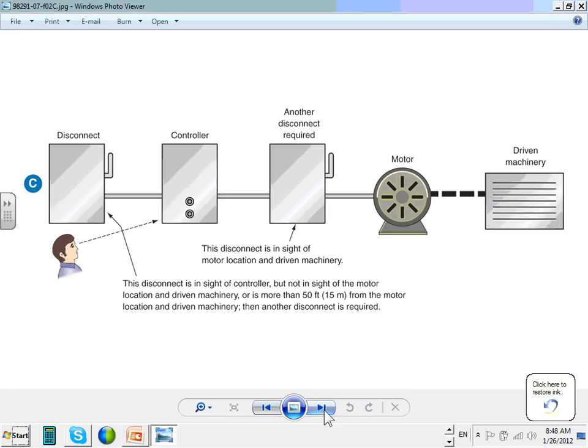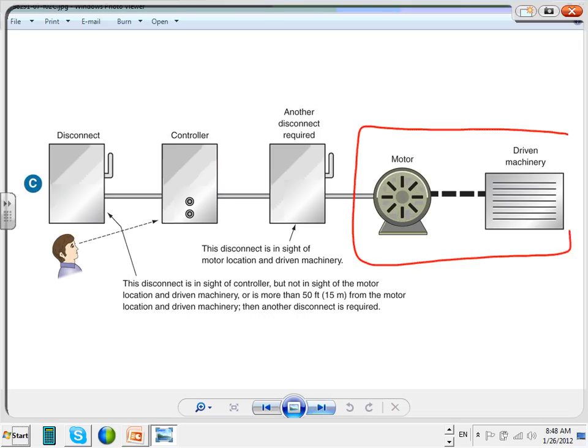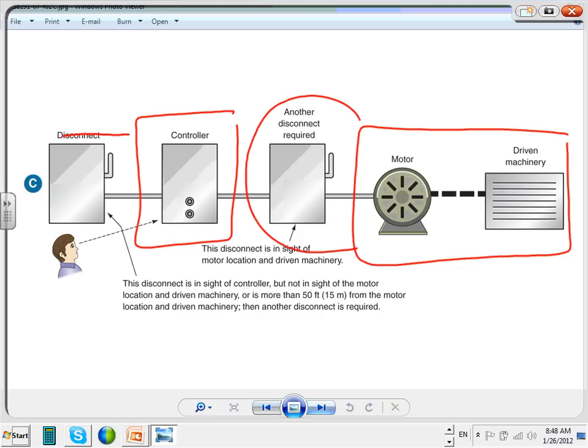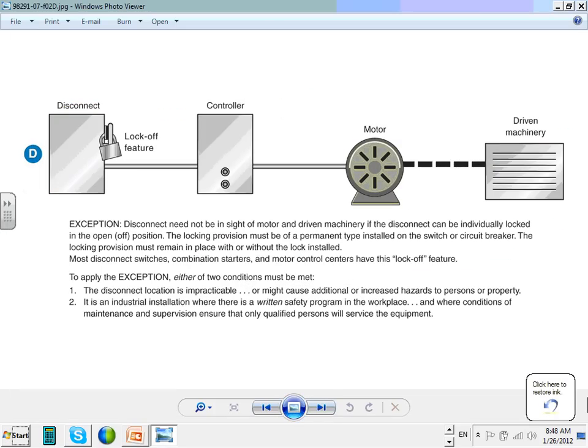Now, what happens under special conditions, guys? Only under special conditions, if you couldn't achieve that, then these will have their own disconnect and the controller. So this goes with this, and the controller is going to have its own disconnect because they are in different locations. You completely want to avoid this. Why? Price? Are you kidding me? You're going to have two disconnects, horsepower rated. So you're going to avoid this. This is bad design, unless you have to. You really want to avoid that. So this is an exception. They use it a lot in industrial and commercial buildings. This is an exception, guys.